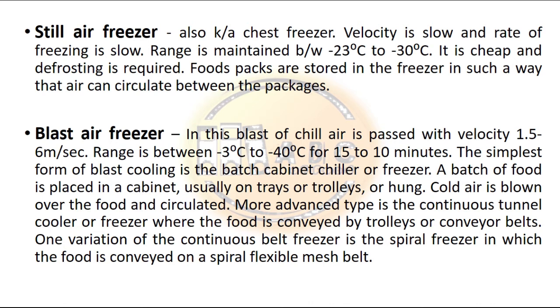The blast air freezer passes a blast of chilled air with a velocity of 1.5 to 6 meters per second. The range is between -3°C to -40°C. The simplest form is the batch cabinet chiller or freezer where a batch of food is placed in a cabinet, usually on trays, trolleys, or hung. A more advanced type is the continuous tunnel cooler or freezer, where food is conveyed by trolleys or conveyor belt. One variation is the spiral freezer, where food is conveyed on a spiral flexible mesh belt.